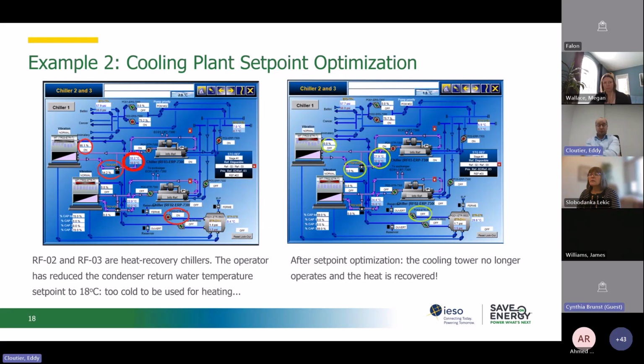Here's another example. In this case, we had a cooling plant that operates in the winter season due to process loads. In municipalities, for example, this is the type of situation that will sometimes happen, for example, in arenas and certain large buildings, which must provide air conditioning 12 months a year for a server room, for example. So in this case, the chillers and the chilled water network had been designed to reject their heat into the heating network at low temperature, which is a very common energy saving measure now in most buildings, I'd say. Excess heat from a system is reused to provide part of the heating of the building.